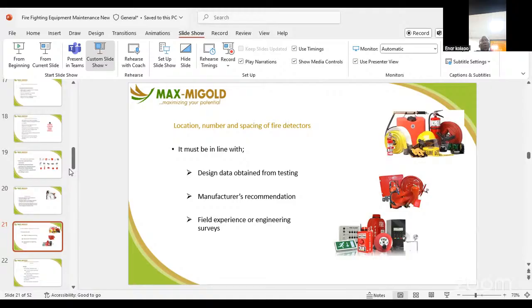But where there are pillars, beams, shelves, things stored, then we need to take into consideration what we call use of space, to estimate the number of smoke detectors that should be there. With use of space, we consider what you are storing in that space, the number of hours that people will be occupying that space, the beam or interference within the space, and a couple of other things that we'll consider as professionals. So we said we should look at the design obtained from testing, field experience or engineering survey, which I've told you has to do with the design and the use of space. Then, of course, what the manufacturer is telling us, and again, what NFPA 72 is telling us. Next slide.